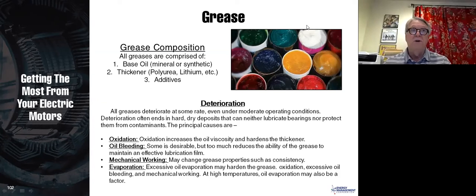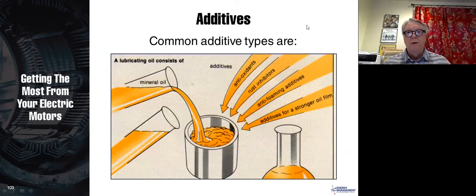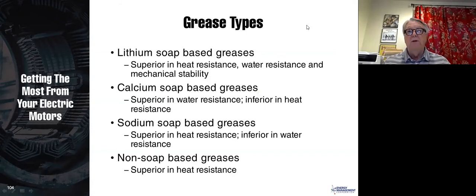And so if you don't grease it, typically the manufacturers tell us you should plan on a 3-year life. That, of course, is assuming that the motor is running 24/7. So if you want your motor to run years and years and years, then you'll need to get a motor that is regreasable. These are some of the additives that you get: antioxidants, rust inhibitors, anti-foamers, additives for a stronger oil film. Here's some of the grease types.